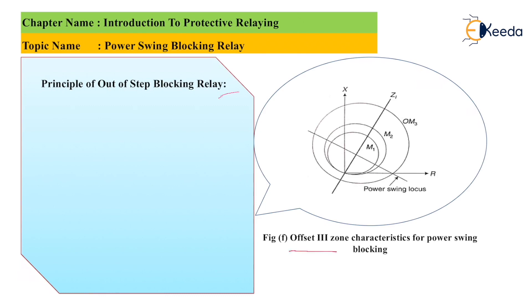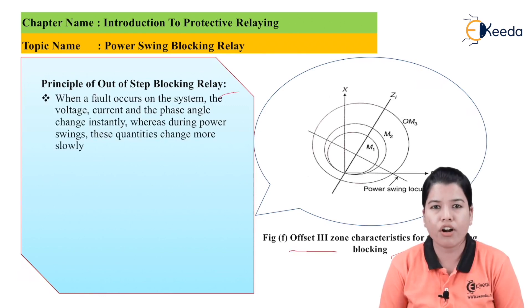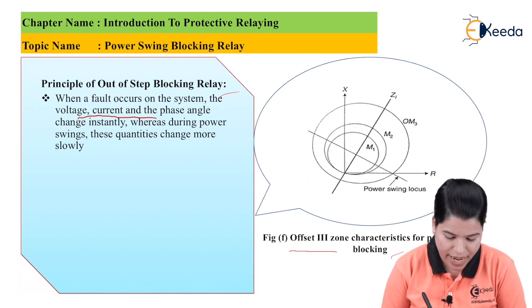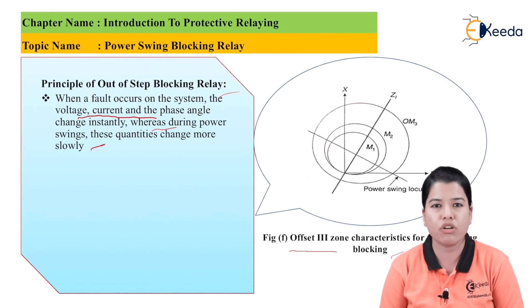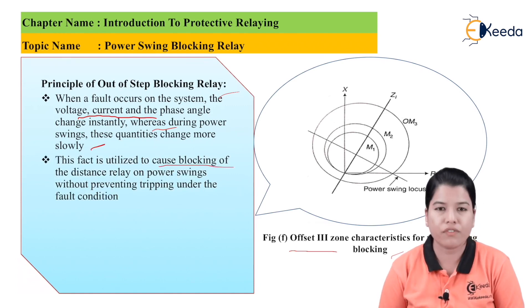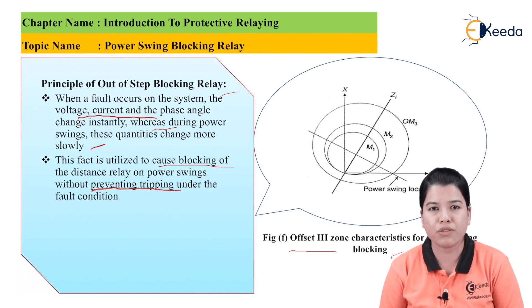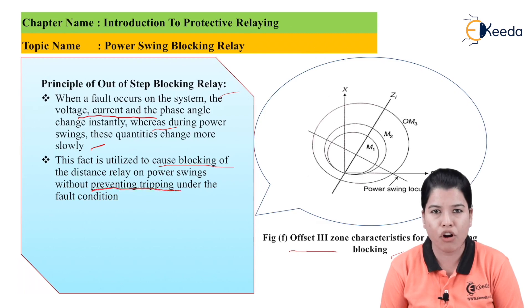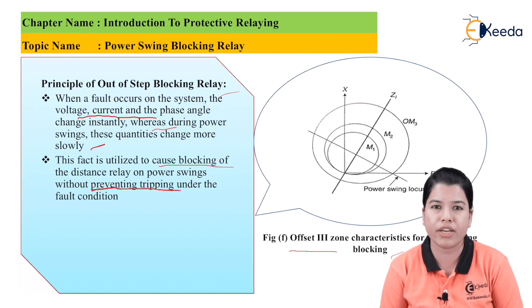Now let us study the principle of the out-of-step blocking relay. The diagram shows offset three-zone characteristics for power swing blocking. When a fault occurs on the system, voltage, current, and phase angle change instantly, whereas during power swings these quantities change more slowly. This fact is utilized to cause blocking of the distance relay during power swings without preventing tripping under fault conditions, since power swing is not considered a fault condition.